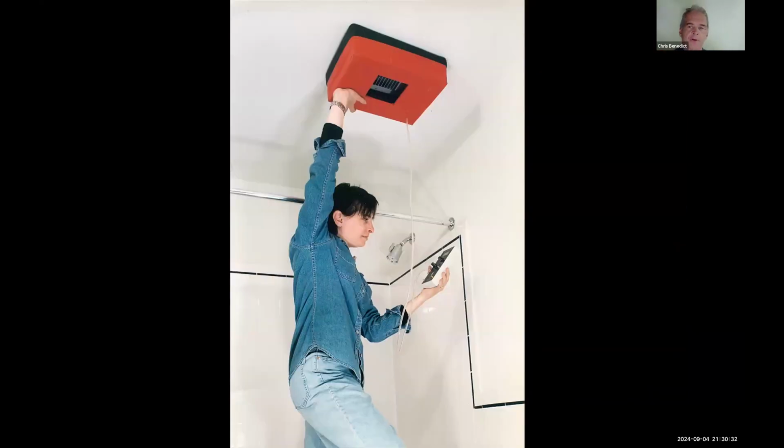This is the only accurate way to measure airflow. That's a manometer in our hand. It measures small air pressure differences, and we're measuring the pressure drop across that square hole. The pressure drop and flow relationship across the square hole is known. So this only works for exhaust, not for a supply grill, because the supply is too turbulent. We made this out of cardboard, but now you can buy them. The Energy Conservatory sells them.